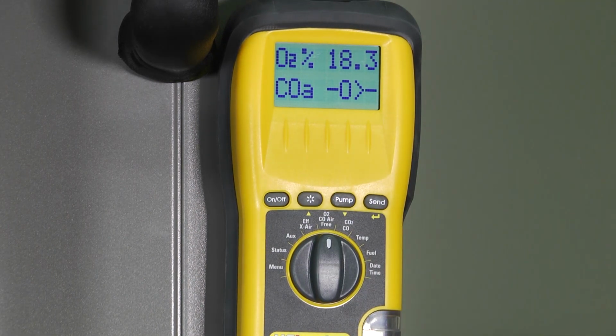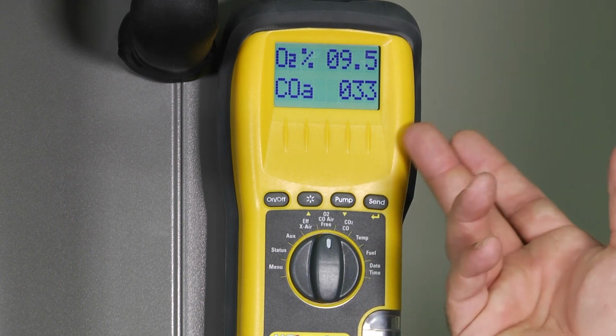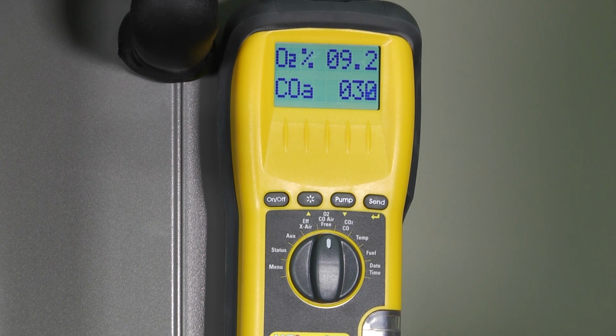But you can see now that my pump is kicked in, I've actually started to reduce the amount of O2 that's in my system. And really my CO air free is starting to climb. So you can see the difference: I've got my O2, which is at 20.9, which is standard room air. That's with my oxygen and all the nitrogen and everything else that's left in it. And my CO in this case is running 30, 32, somewhere in that range, well below the 50 that we call acceptable, and much lower than the 200 parts per million that AHRI says is acceptable.